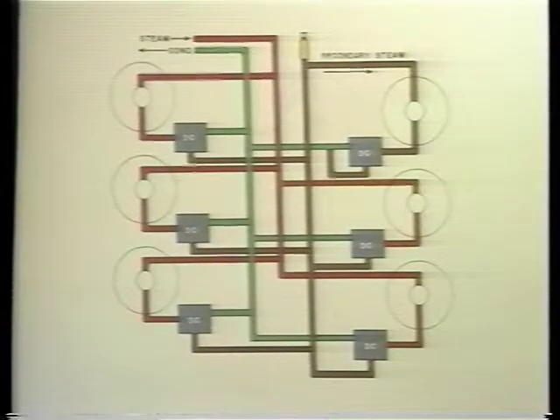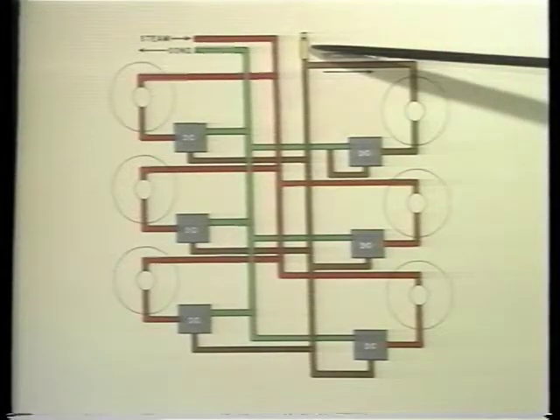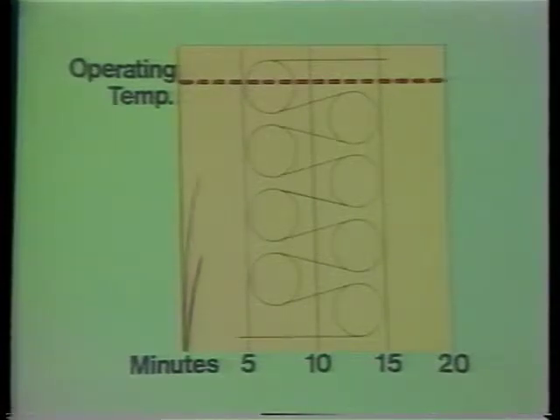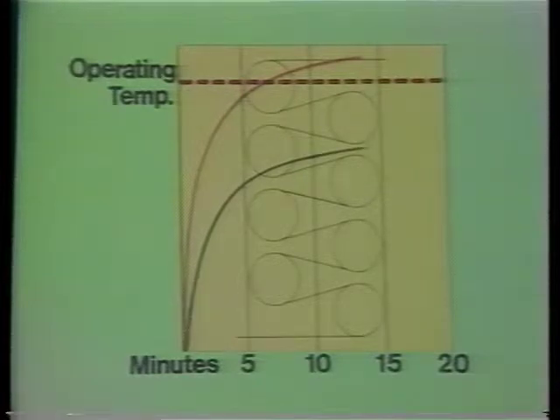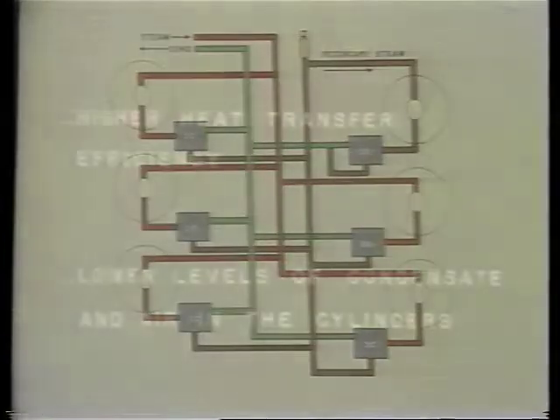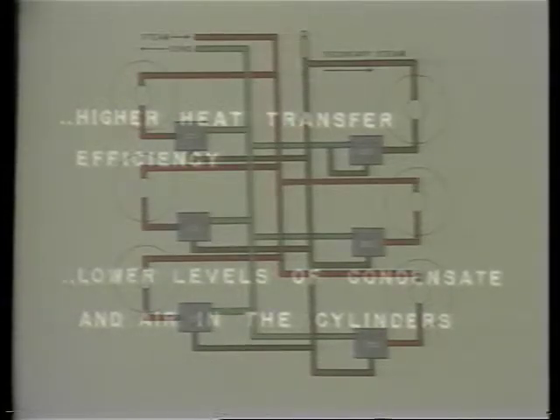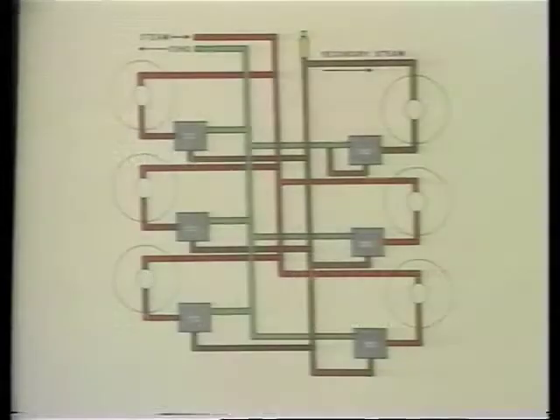In conventional systems, air is returned to the boiler along with the condensate. With the HeatTech system, it is removed at the cylinders, minimizing corrosion and deaeration problems. Tests have proven that the HeatTech system is capable of reaching operating temperature in 10 minutes, as opposed to the 1 to 3 hours required with a conventional system. Higher heat transfer efficiency is made possible by carrying lower levels of condensate and air in the cylinders.